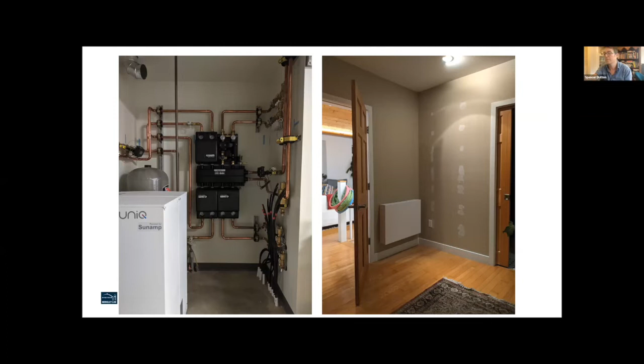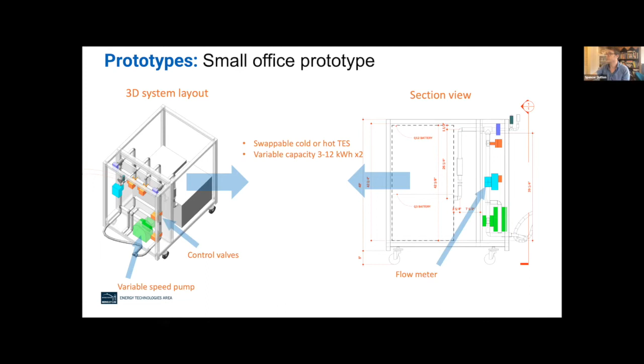We've built a prototype targeting small commercial buildings that we can use to test their operational functionality in the field. The key features are that it will have hot or cold or both thermal energy storage. Those are relatively easy to reconfigure, and we can have up to 24 kilowatt hours of thermal storage capacity. For context, 24 kilowatt hours is roughly equivalent to what you'd store if you were storing heat in 120 gallons of hot water. But because the Sunamp batteries use phase change material, they store that energy as latent heat in addition to sensible heat. The batteries take up approximately a quarter of the volume of an equivalent water tank.